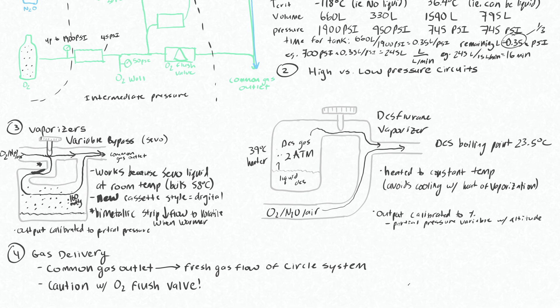After running through the flow meter and the vaporizer, your gases will go to your common gas outlet, which then goes to the fresh gas flow of the circle system. We'll talk about that in the next video. Just to clarify that the common gas outlet shown here is the same gases that are entering through the fresh gas flow.